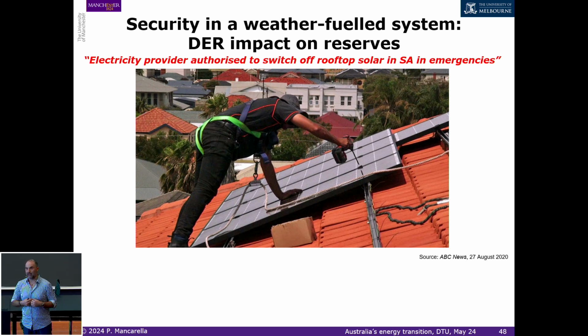Effectively, transmission level issues can propagate down to distribution, and because of the way protection mechanisms work for distributed energy resources, they could also disconnect because the rate of change of frequency is too high. You can have problems with voltages, vector shift protection, or voltage jumps—lots of issues that can happen.